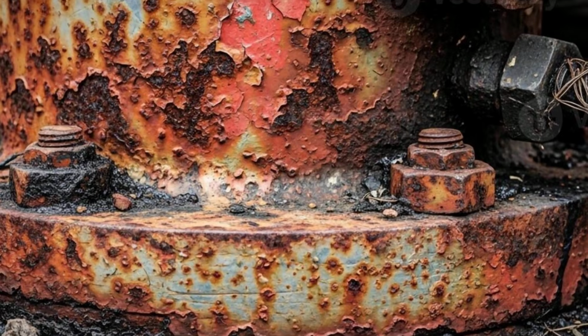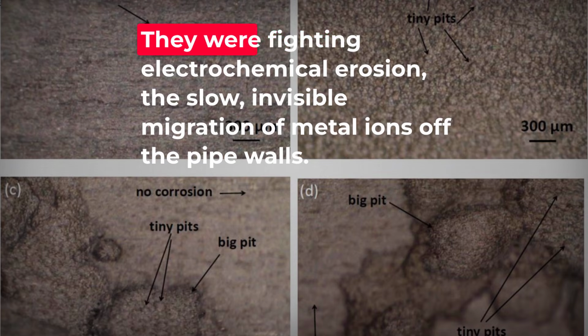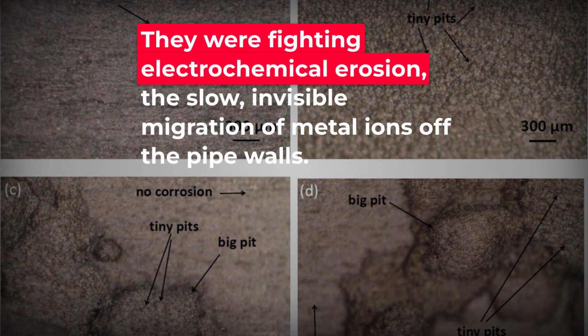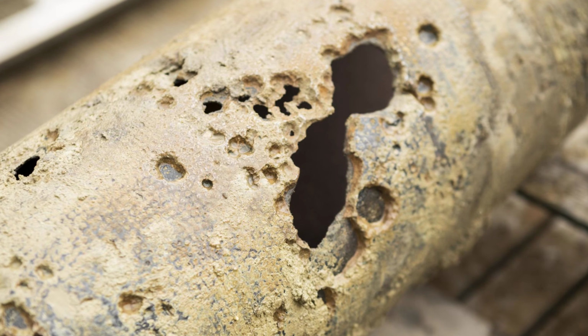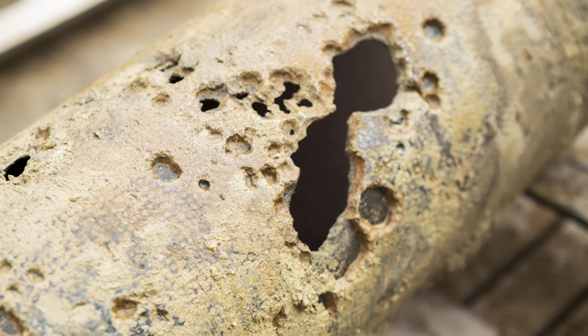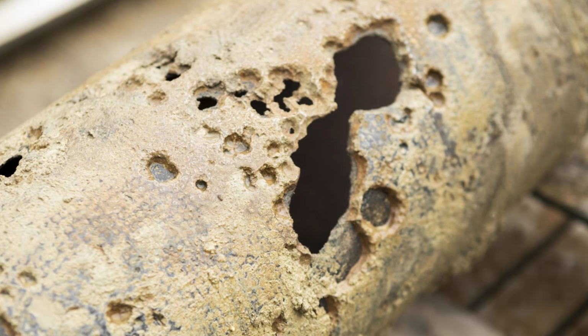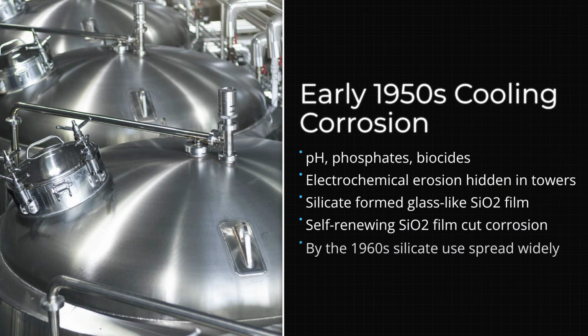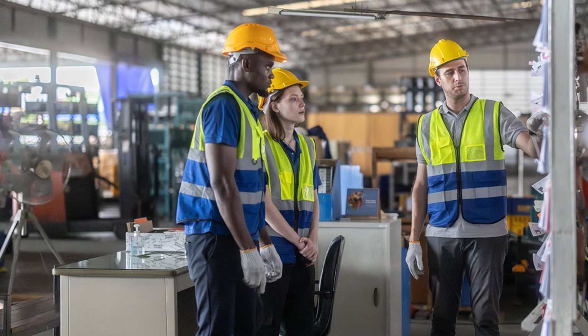They weren't fighting rust you could see and scrape off. They were fighting electrochemical erosion, the slow, invisible migration of metal ions off the pipe walls, leaving behind a weakened, pitted surface that eventually failed without warning and without any visible signal beforehand. They tried the obvious solutions: pH adjustment, phosphate treatments, biocides, scale inhibitors. None of them addressed the root mechanism.